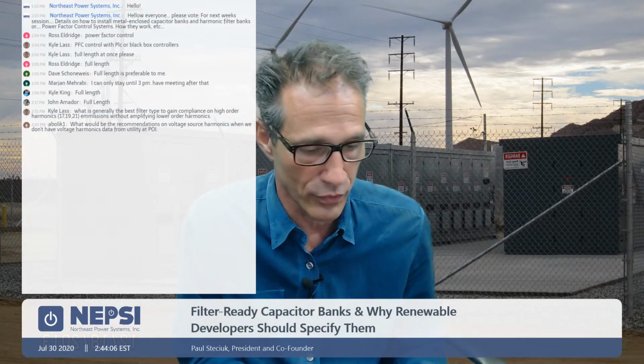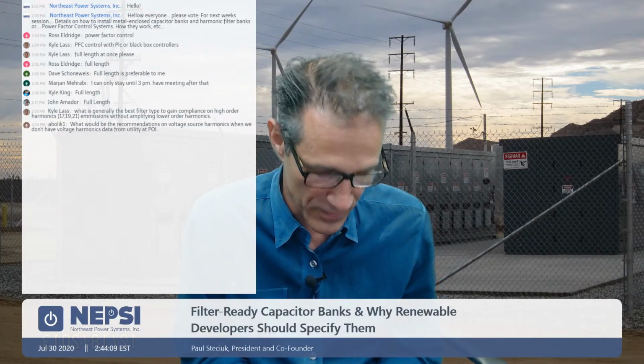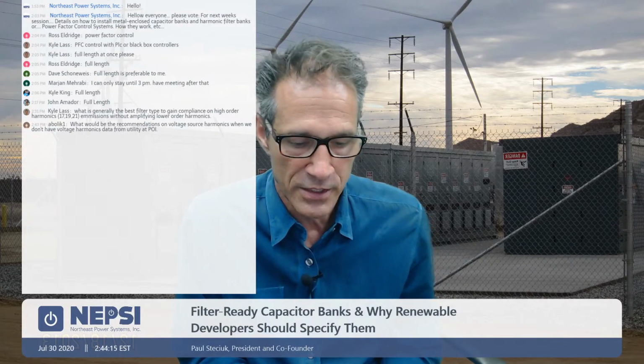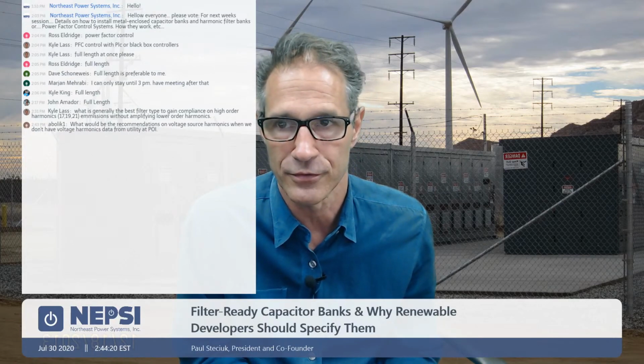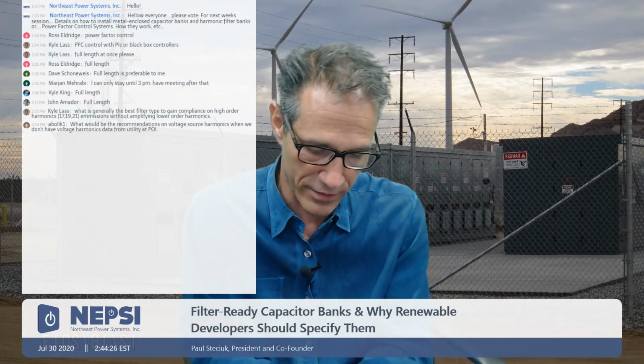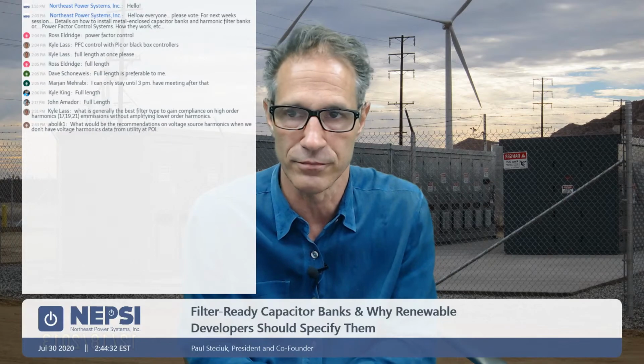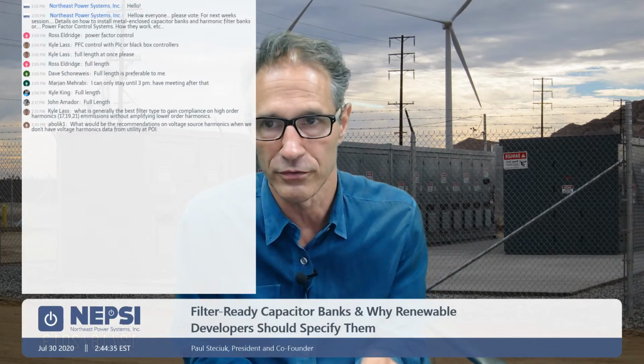Kyle had asked the question, what is generally the best filter type to gain compliance on high order harmonics, 17, 19, 21 emissions, without amplifying lower order harmonics? Well, for sure, it's a C high pass filter or a high pass filter. Remember, high pass filters are generally used at frequencies above the fifth. Let's make sure I get it right because I might misspeak. High pass filters for tuning frequencies above the fifth, C high pass filters for the fifth and below.